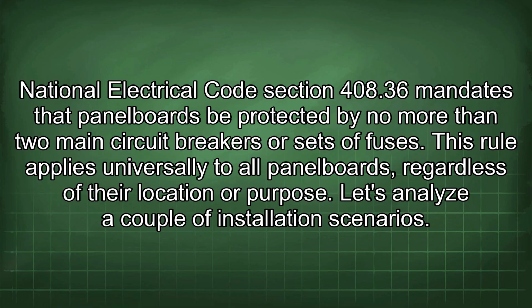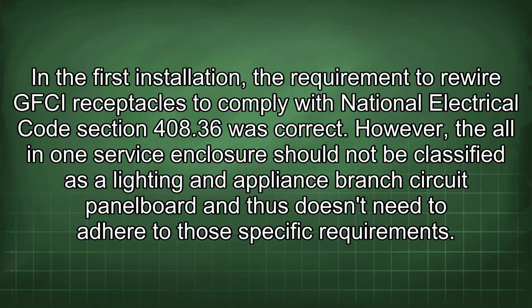Let's analyze a couple of installation scenarios. In the first installation, the requirement to rewire GFCI receptacles to comply with National Electrical Code Section 408.36 was correct. However, the all-in-one service enclosure should not be classified as a lighting and appliance branch circuit panel board and thus doesn't need to adhere to those specific requirements.